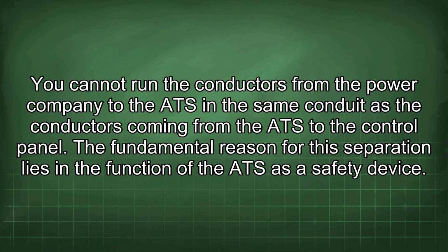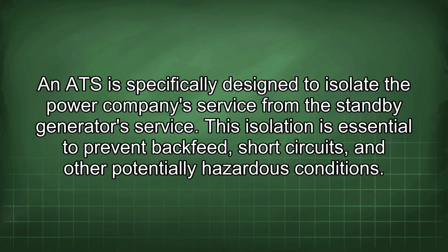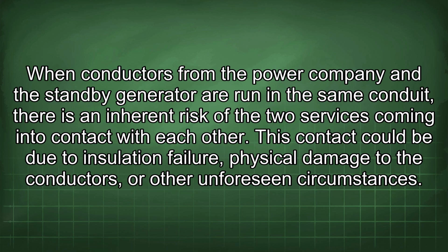The fundamental reason for this separation lies in the function of the ATS as a safety device. An ATS is specifically designed to isolate the power company's service from the standby generator service. This isolation is essential to prevent backfeed, short circuits, and other potentially hazardous conditions. When conductors from the power company and the standby generator are run in the same conduit, there is an inherent risk of the two services coming into contact with each other. This contact could be due to insulation failure, physical damage to the conductors, or other unforeseen circumstances.